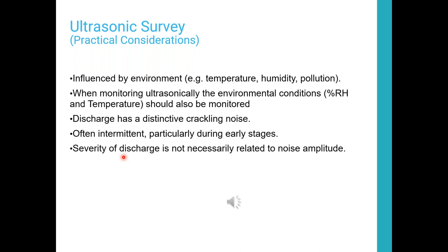It has a very distinct crackling noise. So when you're doing ultrasonics, you're going to have a set of headphones on, listening for ultrasonic emissions. They're often intermittent, particularly in early stages, so you know it's going to come and go. So you listen for this crackling noise. Some people refer to it as very similar to bacon frying in a pan, a popping and spitting. Have you ever seen the old Frankenstein movies, Jacob's Ladders, the buzzing that's created by that? That's going to be similar to the sound you're going to be listening for with surface discharge.